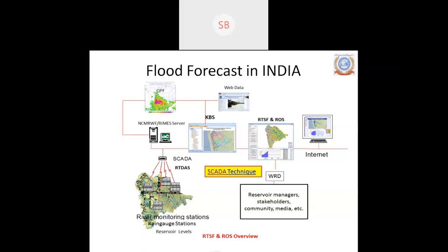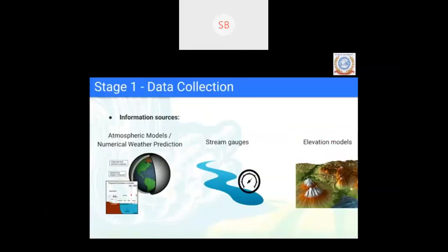Probably this is not a hydrology engineer's interest, but there is an option available to use long ranging spread spectrum communication, which is free of cost, available for low bandwidth data sets. In case your data is more, you should go for a radio with all the radio permissions, so you could transmit, because most of the reservoirs are in hilly terrain where you don't expect a very good quality 4G data network. So if that is ensured, then in the coming years probably we can depend only on GSM GPRS. Else you need to think about radio communications and satellite data also to some extent.